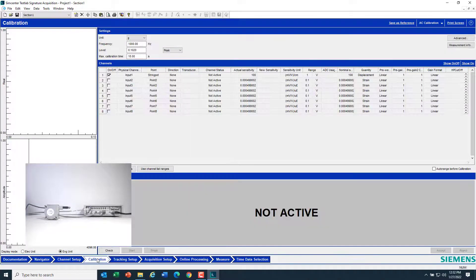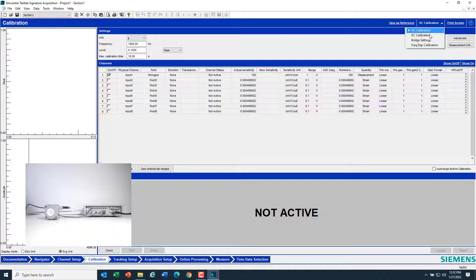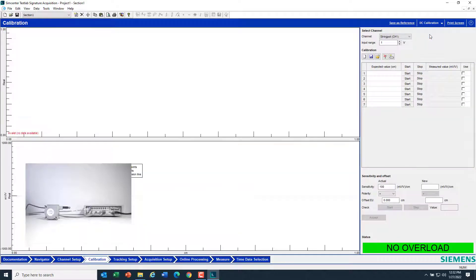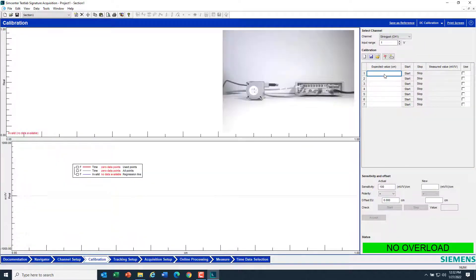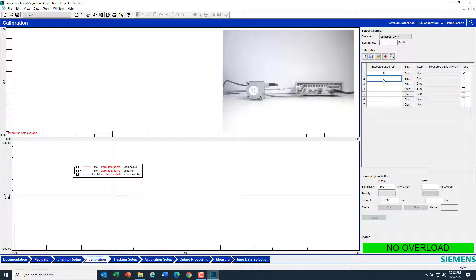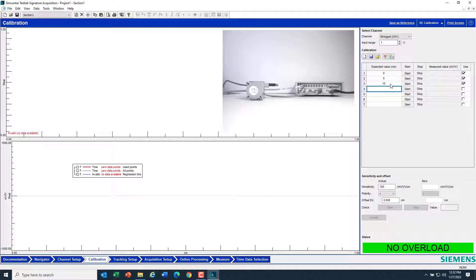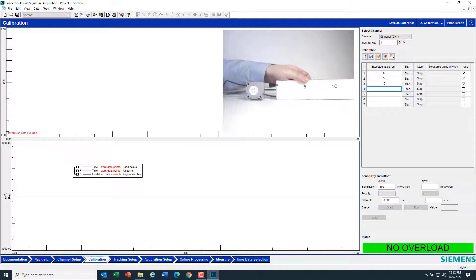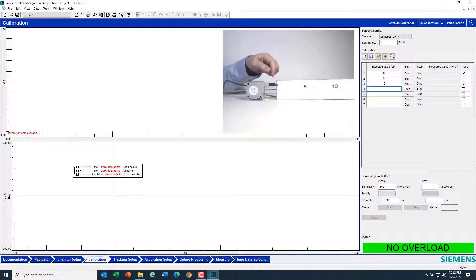I'll go to Calibration next. In the upper right here, I'll pick DC Calibration. I can type some values that I'd like to measure with the string pot to calibrate it. So 0, 5, and 10 here.